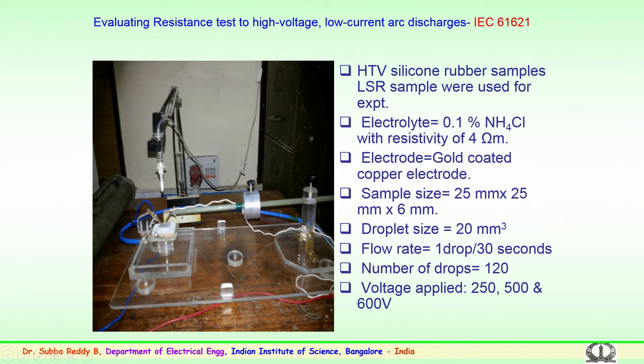is applied continuously over a period of time while the drops fall continuously at regular intervals. You can see that the sample which is kept here could be of HTV silicone rubber, high temperature vulcanized silicone rubber, or the liquid silicone rubber which is used for bushings. So, in the present case 2 types of samples were used for experimentation. The electrolyte or the contaminant consisted of 0.1% NH4Cl with resistivity of 4 ohm meter.